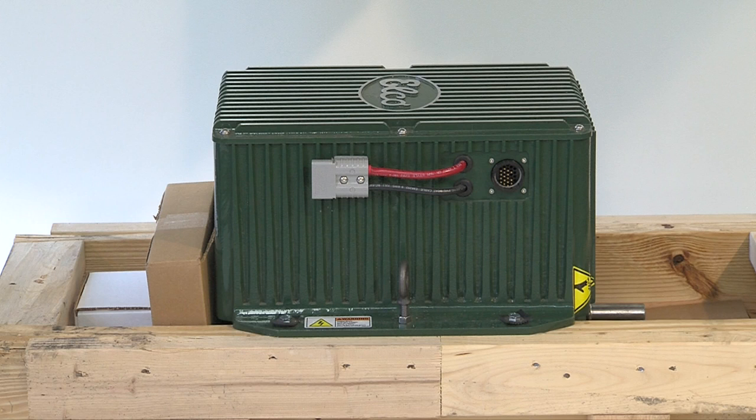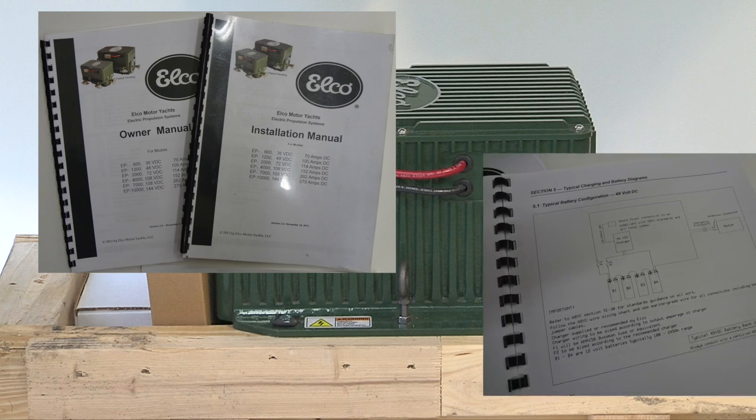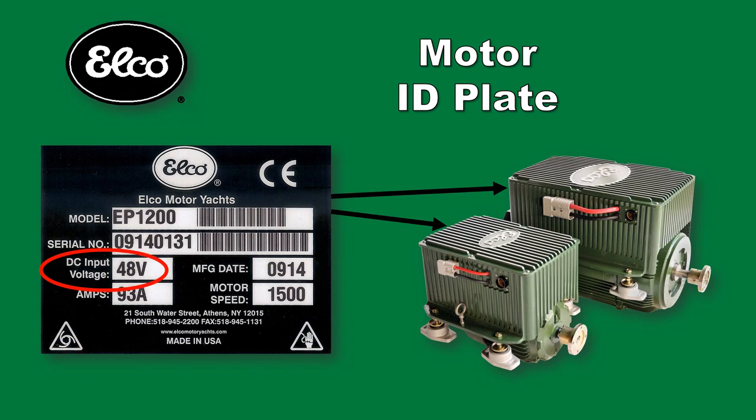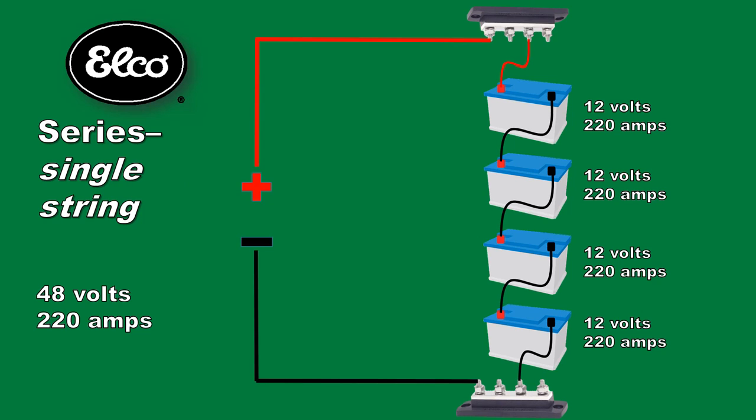When you purchase an Elco EP motor, installation and owner manuals are provided. The installation manual contains a wiring diagram which illustrates what we explain in this video. Confirm your motor voltage requirements by referring to the identification plate found on the motor casting. We are using an Elco EP1200, which requires 48 volts DC. There are 48 volt lithium battery packs available for this application, but we will use AGM batteries instead. 12 volt batteries are wired in series to achieve the required voltage. When connected in series, the voltage of each battery is added, so we'll connect four 12-volt batteries for the required 48 volts. This does not increase the amp hour rating of the string, which remains the same.